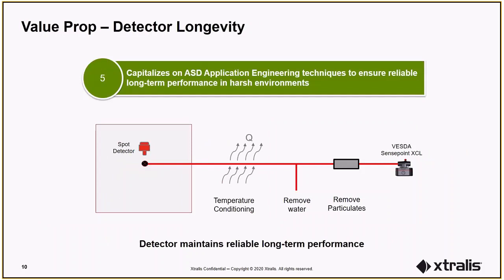Being aspirated, the VESDA XCL can be protected from the harshness of the detection zone environment. Here we can see how the sampling pipe itself and inline pipe components can be used to condition the temperature, remove water and other airborne contaminants from the air before it reaches the detector. Protecting the detector against the harshness of the environment will ensure it performs reliably over the long term.